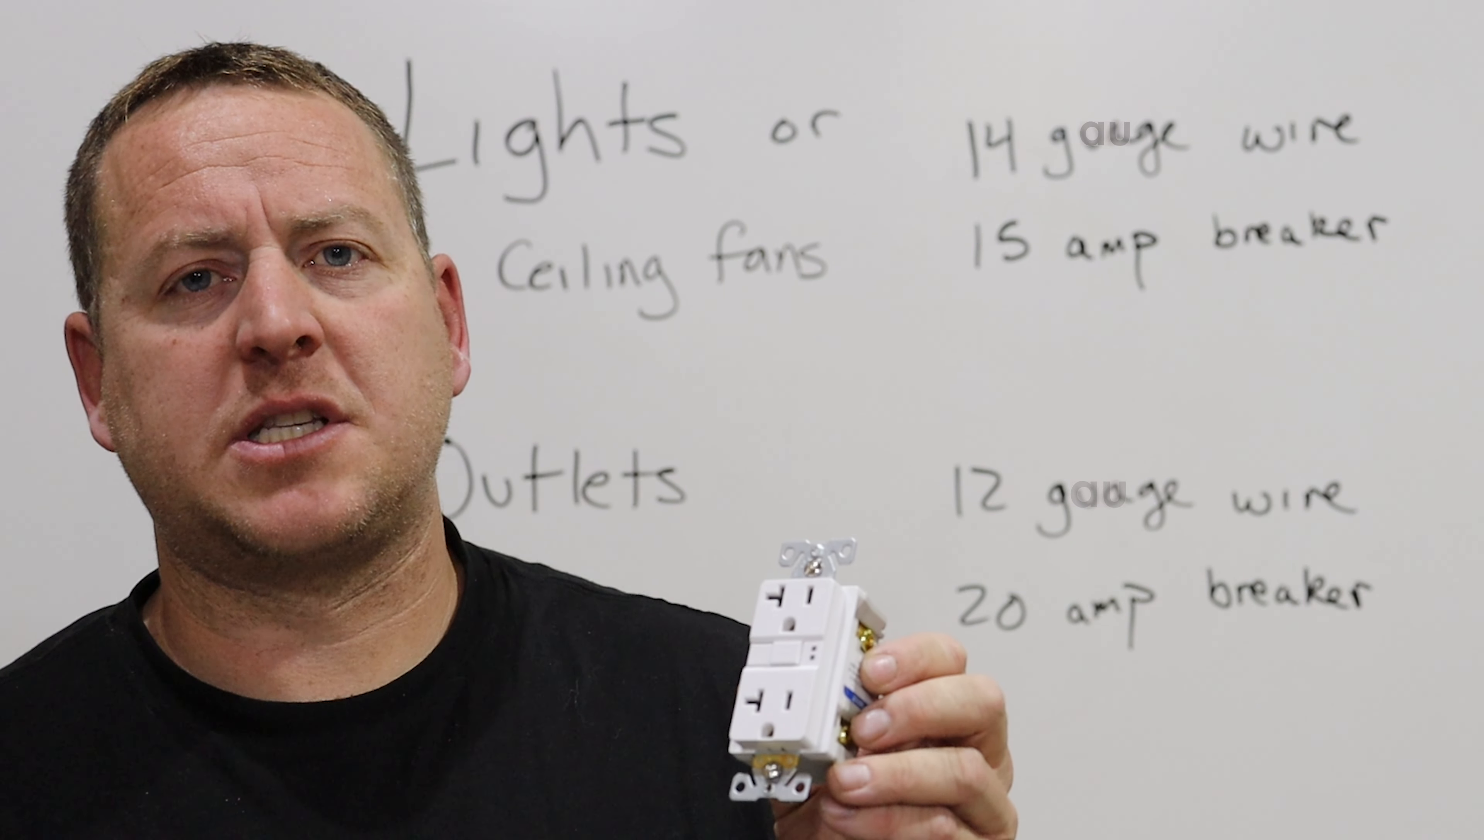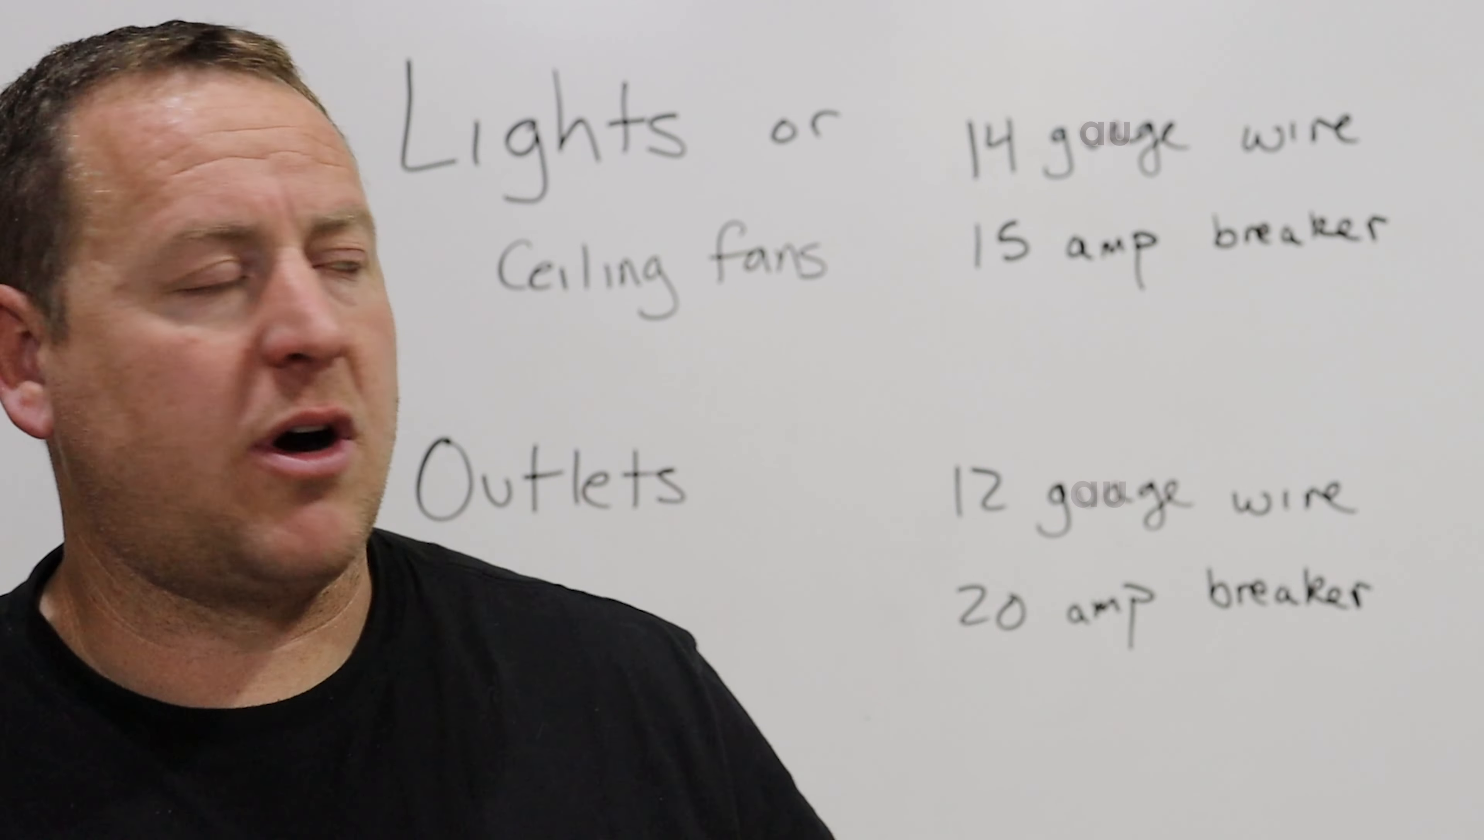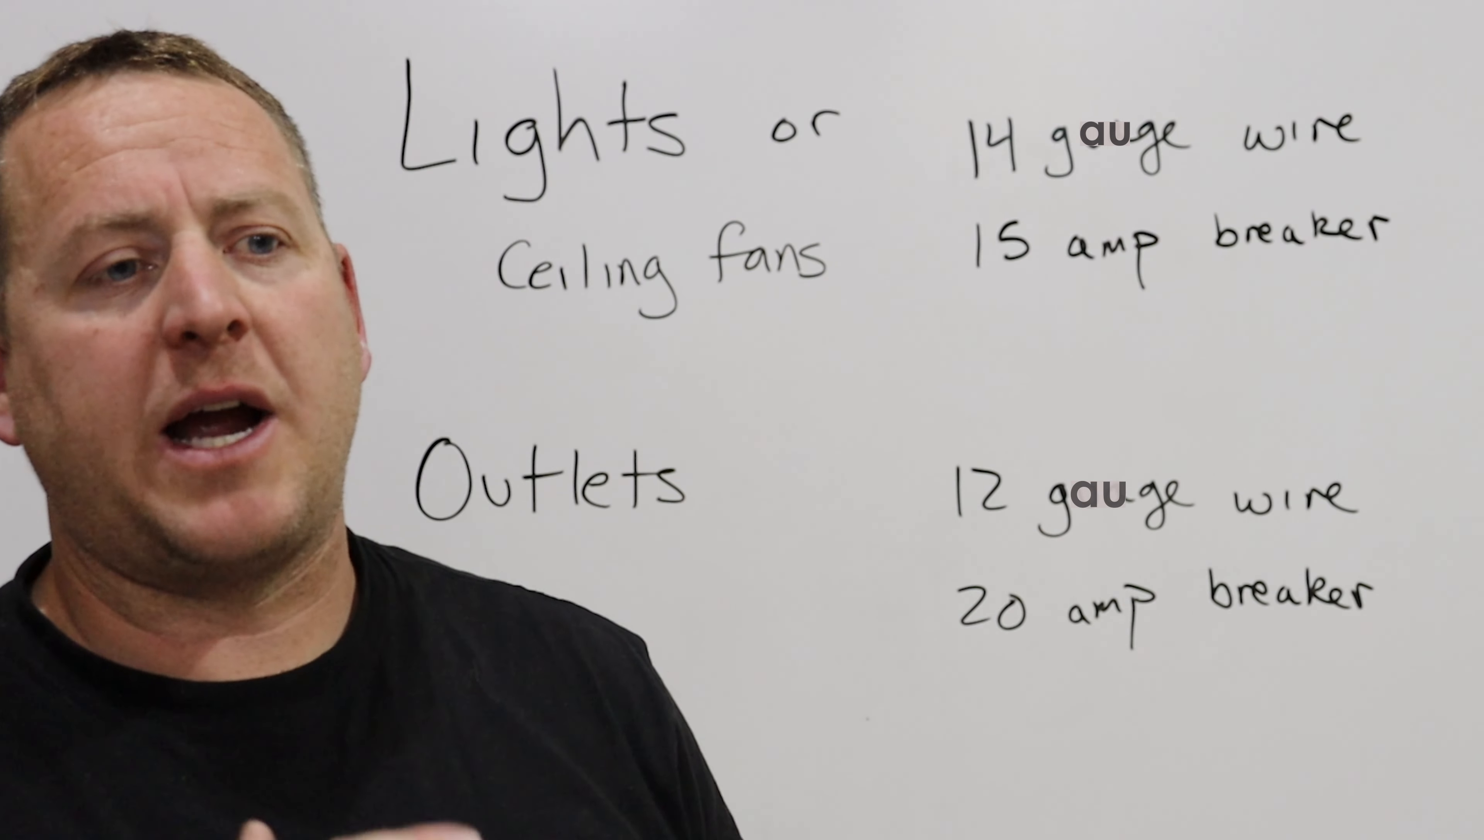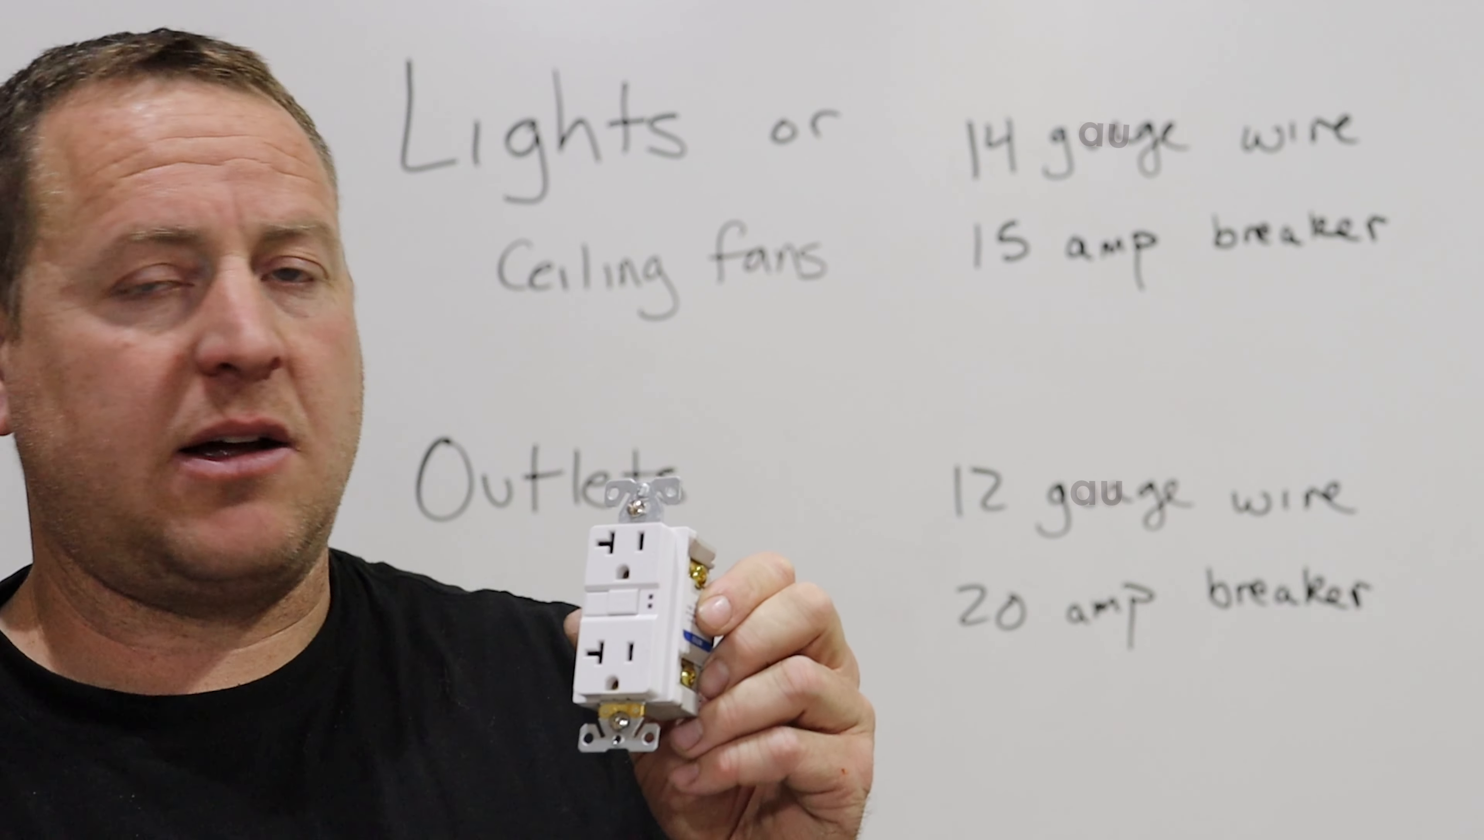Your outlets and switches also have amperage ratings. For all my lights I use 15 amp wire—the 14 gauge wire with a 15 amp breaker. For all my outlets, they're going to be 20 amp, so I got the outlets and the GFCI outlets rated for 20 amps.